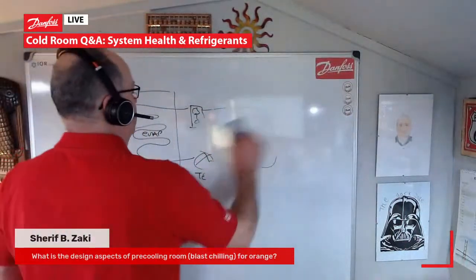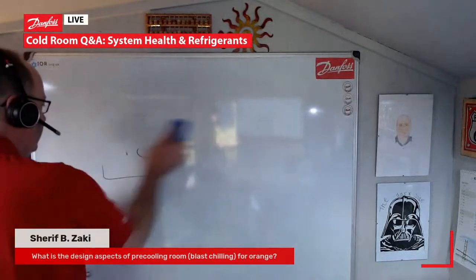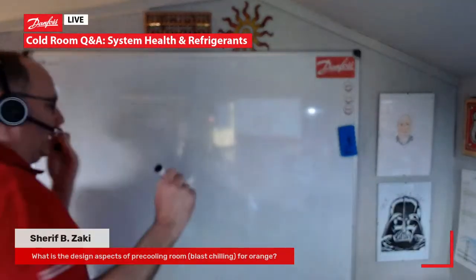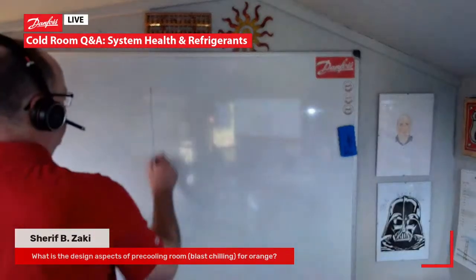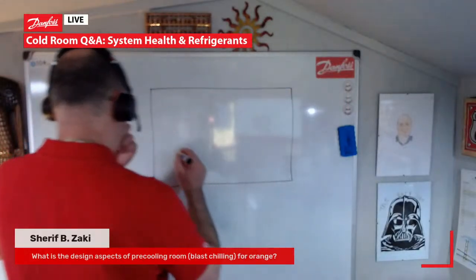Another question's come in from Sheriff. What are the design aspects of a pre-cooling room, blast chilling for orange? Yeah, that's a good question. I mean, the basics of blast chill or blast freeze for that matter. If we talk about a cold room as such, or a blast chill, blast freeze, I'll just show a basic one. And again, this depends, actually. This is quite an interesting question. Is it orange juice, or is it oranges, the fruit? If it was orange juice, then it would go through some form of plate heat exchanger to cool it down.